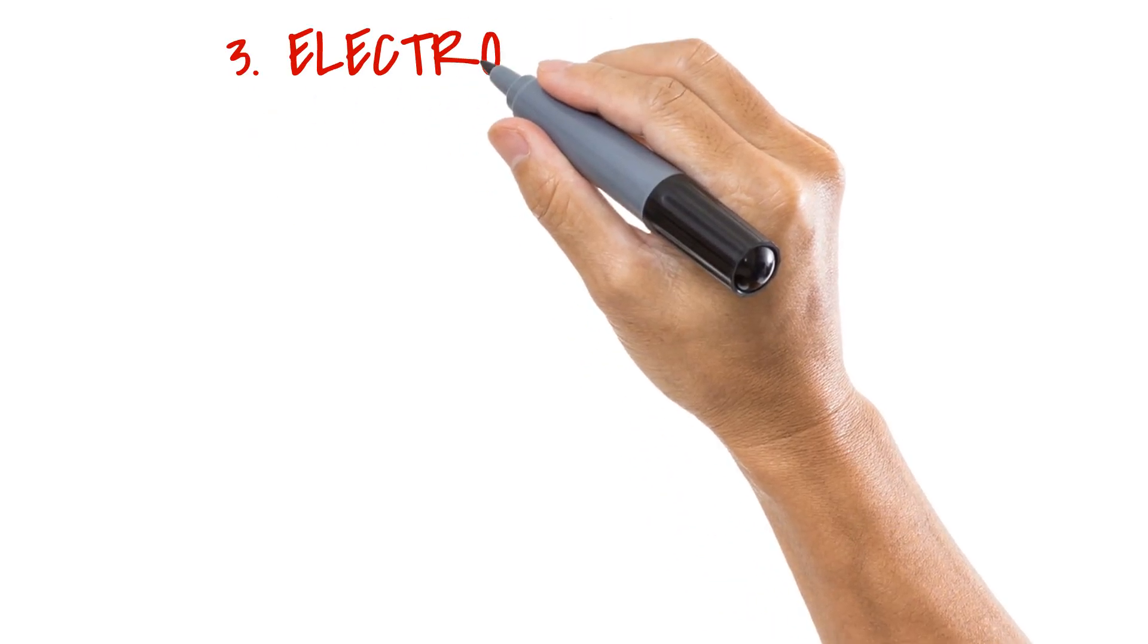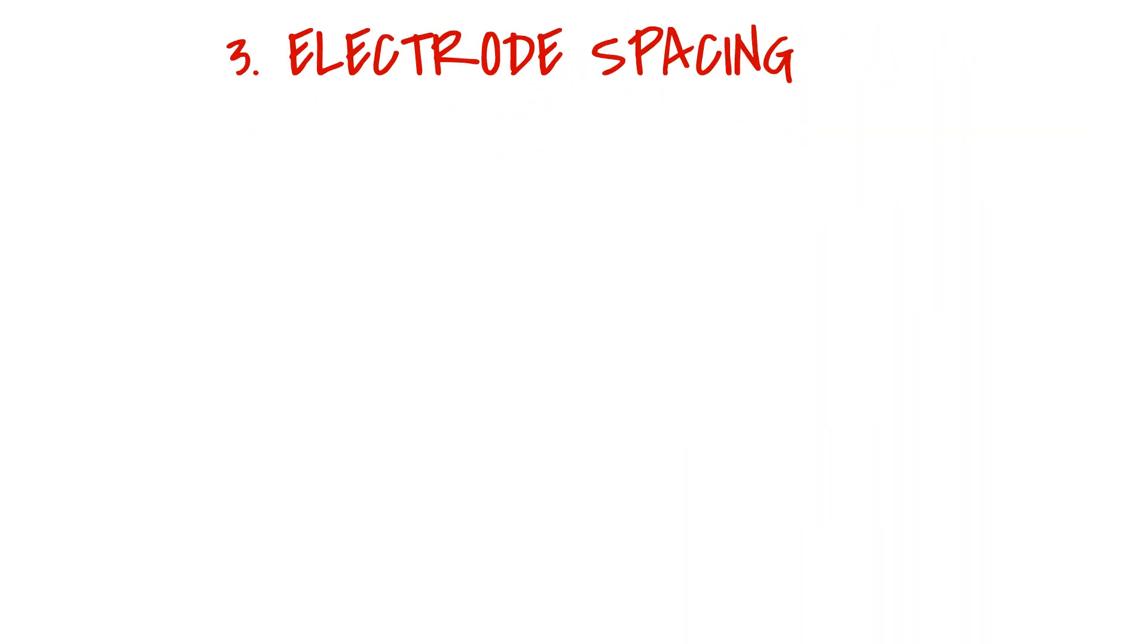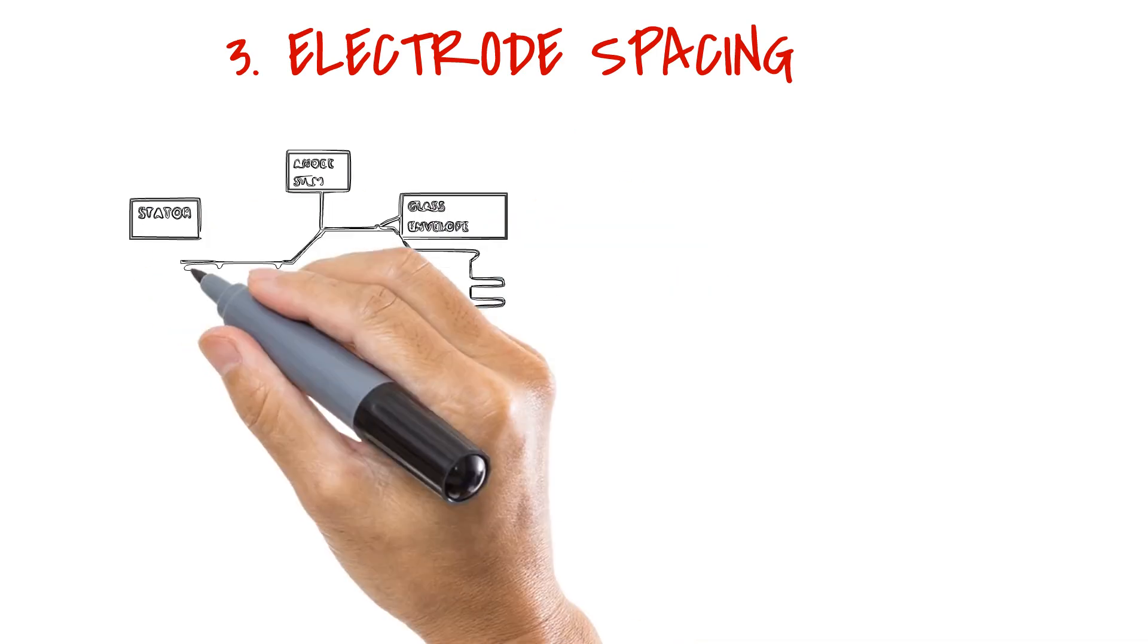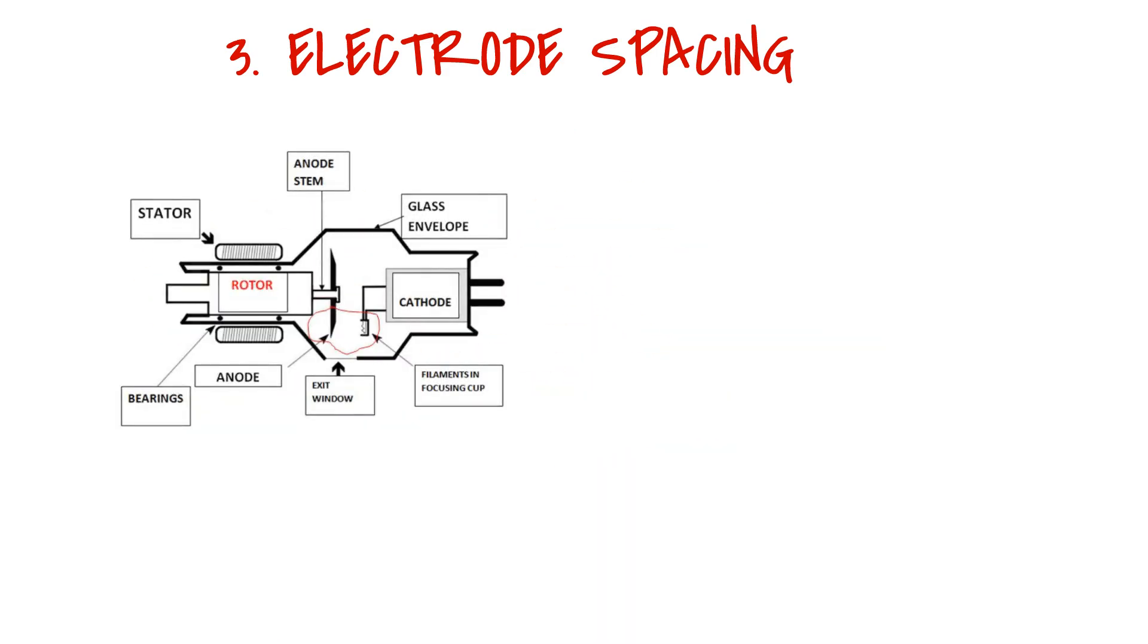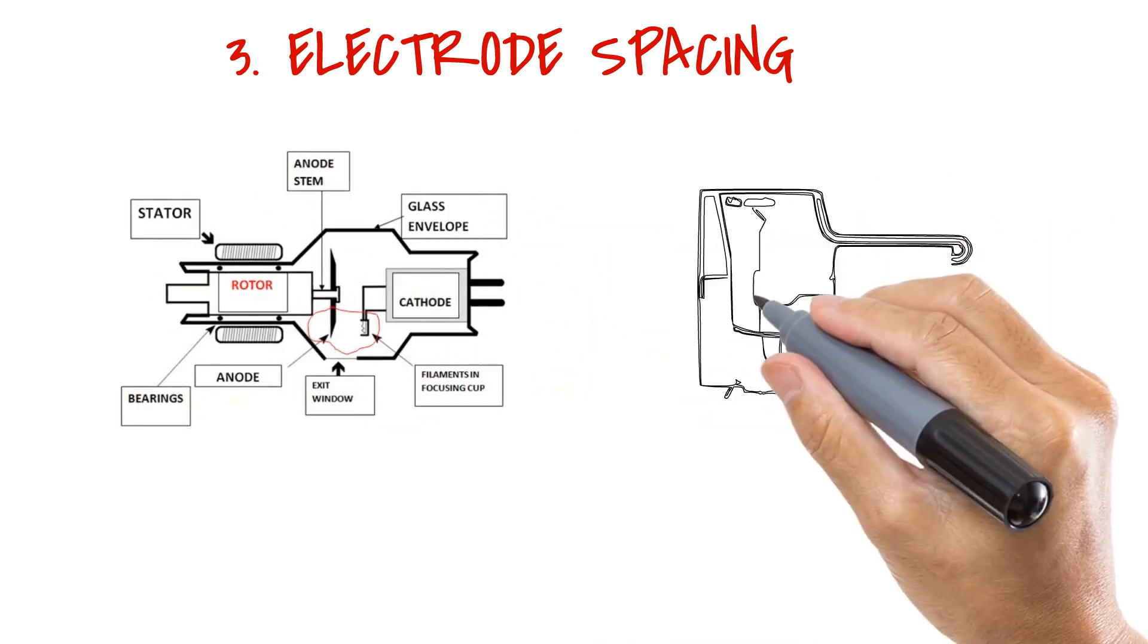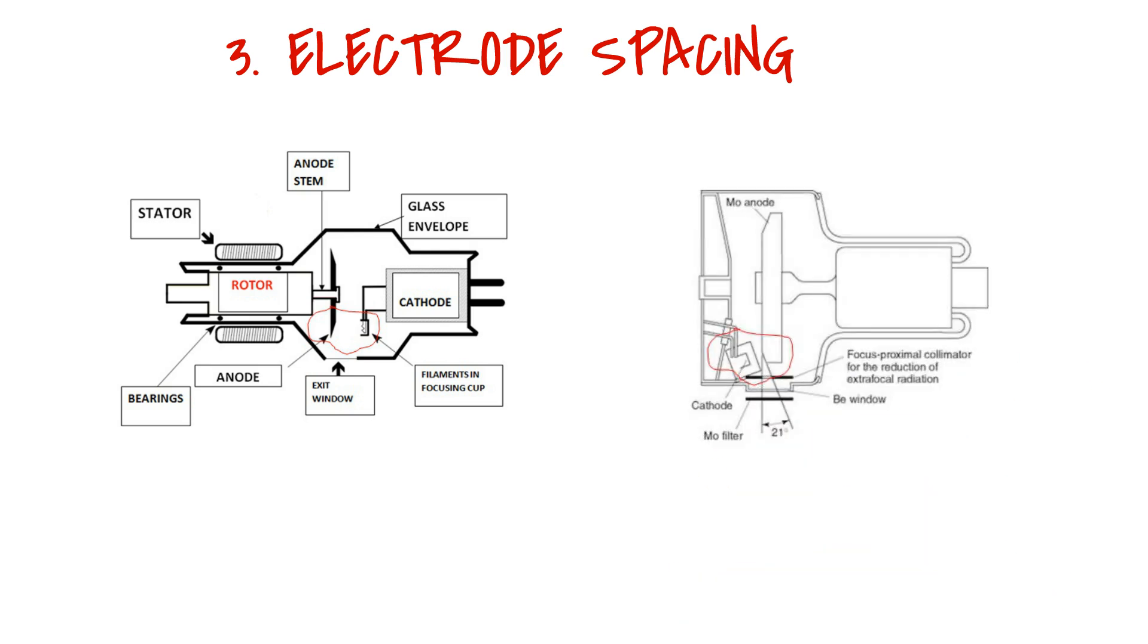Another modification made to the mammography tube is the distance between the cathode and anode of the tube. Because of the low kilovoltage used in mammography, the force that attracts electrons from cathode to anode is smaller. Thus, the cathode and anode in a mammography tube are made to be closer to allow this weak attractive force to be sufficient for transporting electrons from cathode to anode. This also provides the advantage of having smaller X-ray tubes in mammography.